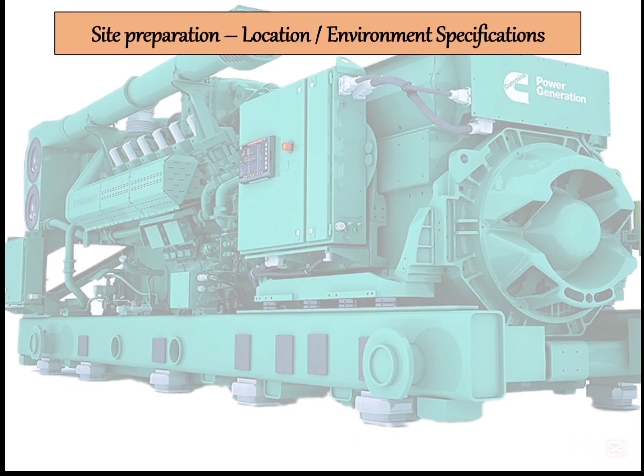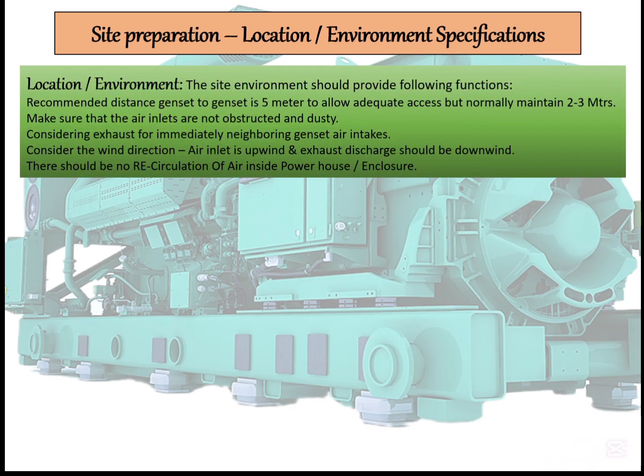The next crucial part is location and environment specification. For gas engines, the environment should be clean. When installing the genset, the recommendation is a minimum distance of 5 meters between two gensets, which allows adequate access for maintenance, cooling, and air passage. In areas with space constraints, at least 2 to 3 meters should be allowed to install the genset. The atmosphere should not be dusty, and if it is dusty, then we need to arrange some filters, because a gas engine needs fresh air for combustion.